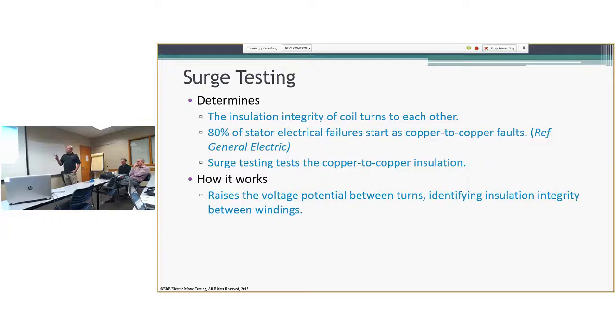80% of stator electrical failures start as copper to copper faults. And that's that video we showed you earlier with the smoke coming out. It was just the induced turn short, and it took like a minute before smoke started coming out. But the thing is, if we could find that at a higher voltage than 480 volts, so we can find it at 1,000, 1,200, 1,500 volts, that's what we want to do, because to let you know that, hey, eventually it's going to happen at 480 and your motor's going to fail in minutes. But if we find it up in those higher ranges, it gives you a longer time to think about changing that motor out.